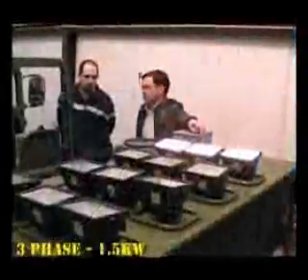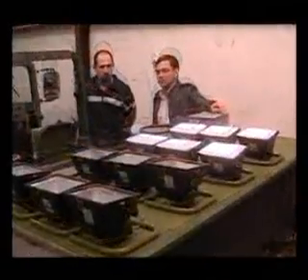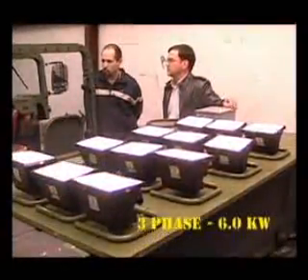Demonstrations were held to show the VPS-10K in an actual retrofit of a Humvee. During the first phase of these demonstrations, the load was a light bank that represents up to 6 kW of power. And in this demonstration, the loads were increased per phase as they ramp up from 1.5 kW to 6 kW and then back down. As you can see in the demonstrations, the speed controller reacts to the load, applying the appropriate RPMs based upon the amount of current that's being drawn from the VPS-10K unit.